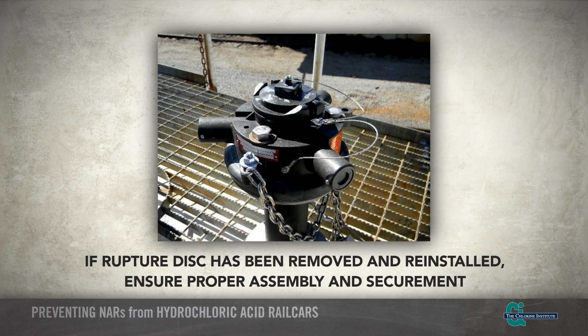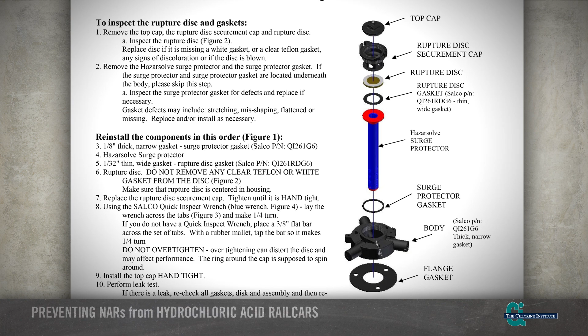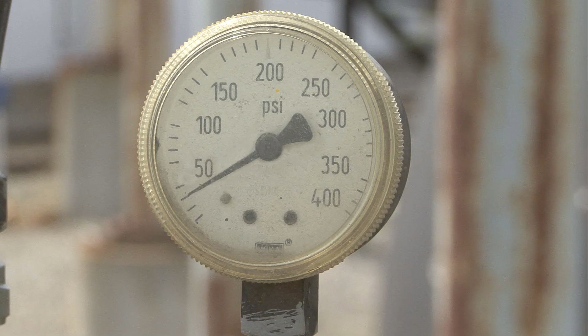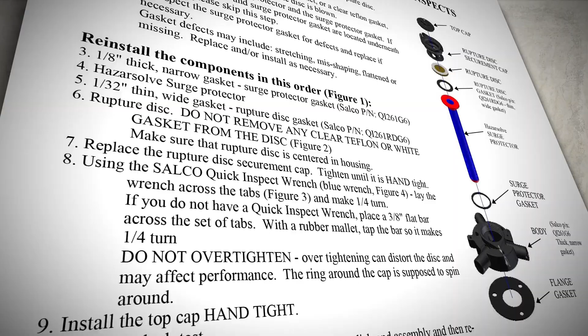After inspection, it is crucial to ensure proper assembly and securement of the rupture disc assembly. Be sure the disc is installed with proper flow direction. Original equipment manufacturers, or OEMs, provide instructions to ensure proper orientation of the disc and housing assembly. You may also conduct a pressure leak check to ensure proper functioning of the rupture disc, in addition to visually inspecting the rupture disc. Here are sample rupture disc assembly drawings and assembly instructions.